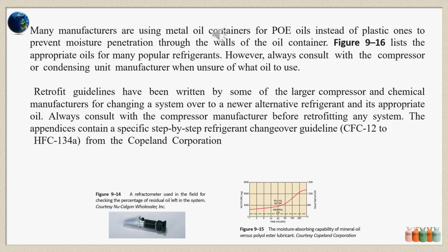Retrofit guidelines have been written by some of the larger compressor and chemical manufacturers for changing a system over to a newer alternative refrigerant and its appropriate oil. Always consult with the compressor manufacturer before retrofitting any system. The appendices contain a specific step-by-step refrigerant changeover guideline, CFC-12 to HFC-134A, from the Copeland Corporation.